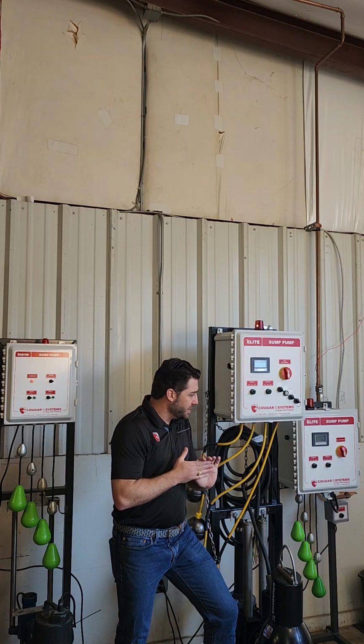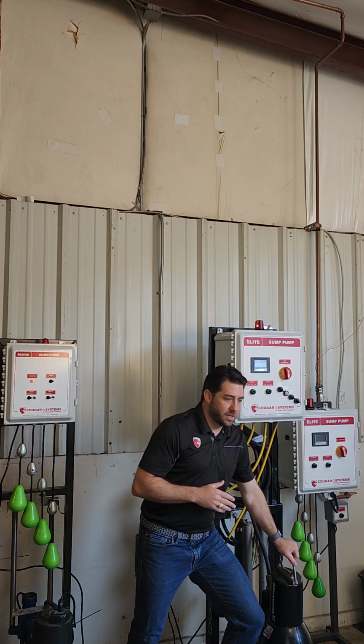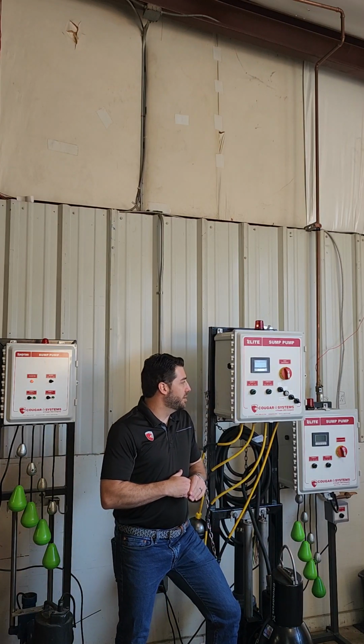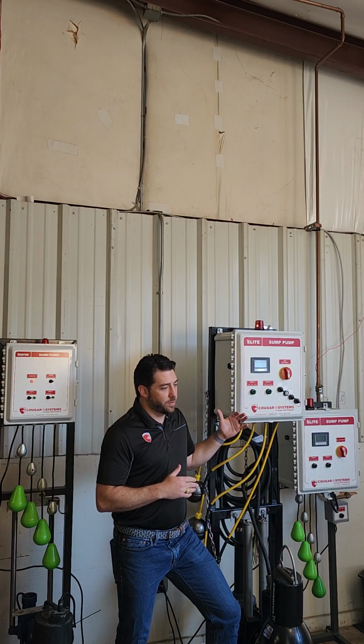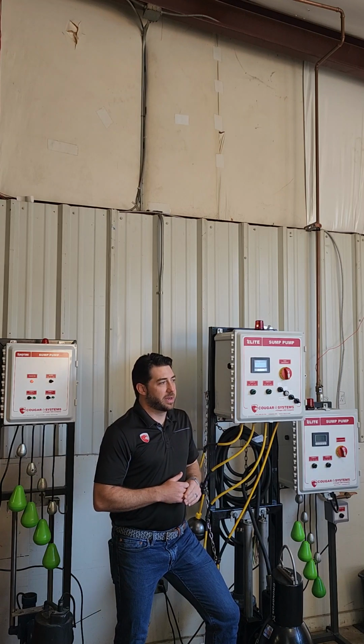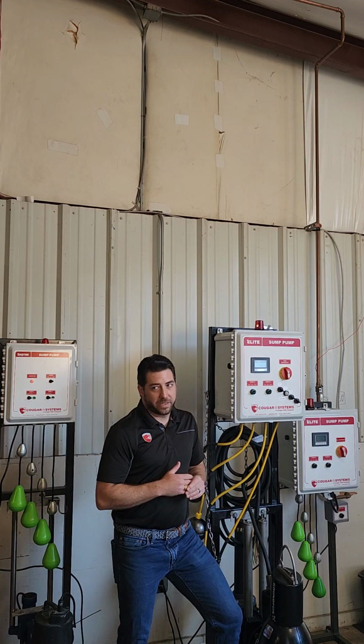So on the storm side, we're going to be moving a lot more water in, potentially, and that's where we get into the 4 float switches, where we might need both pumps to run before we get to the high level water.